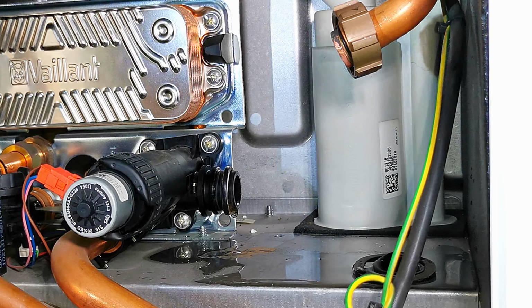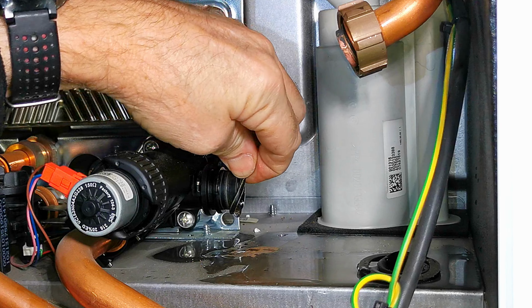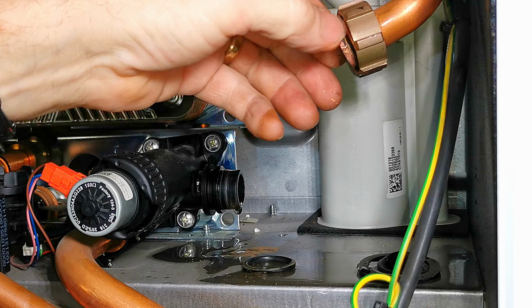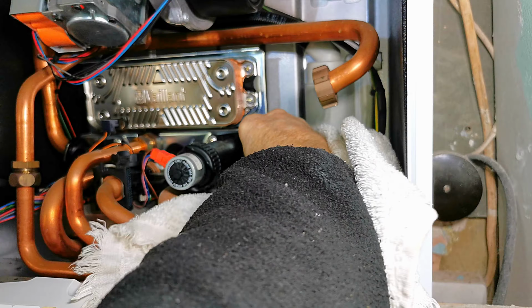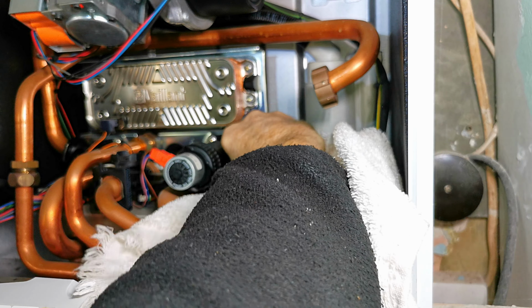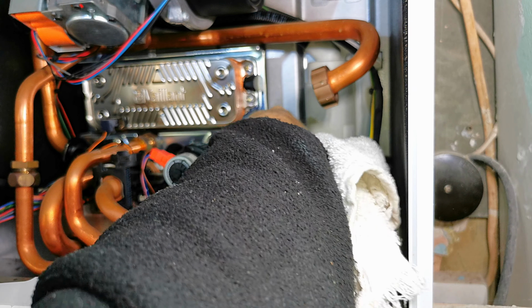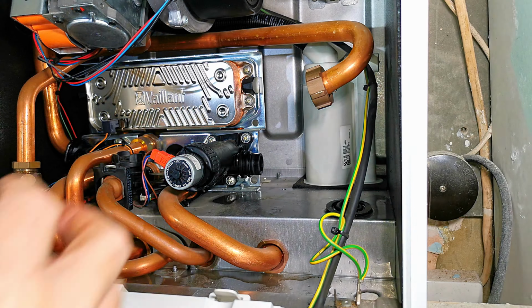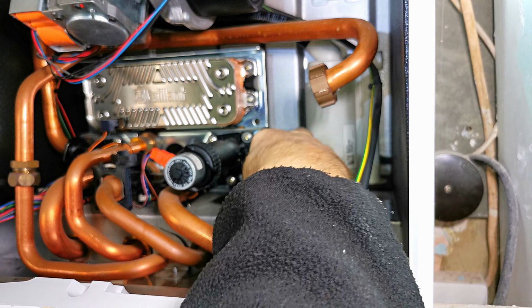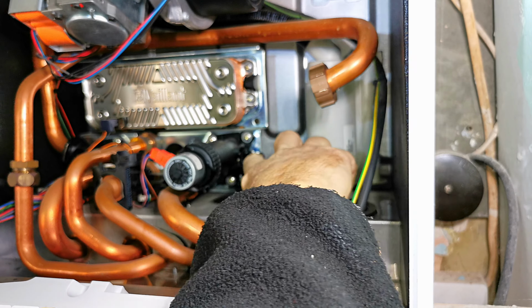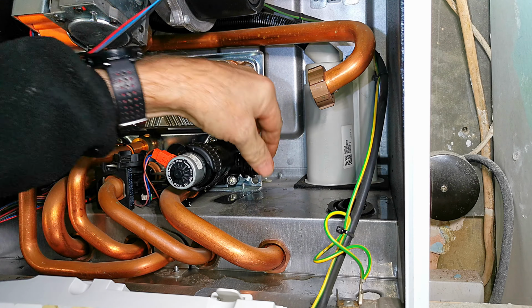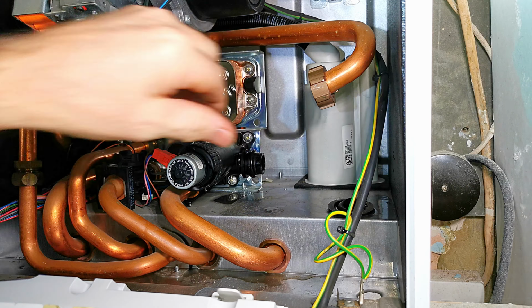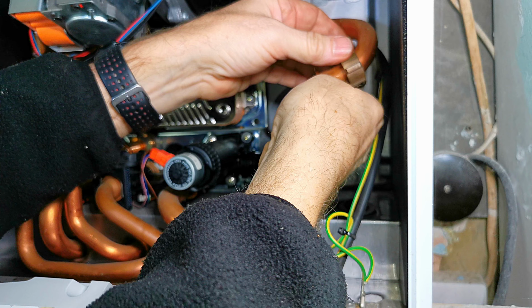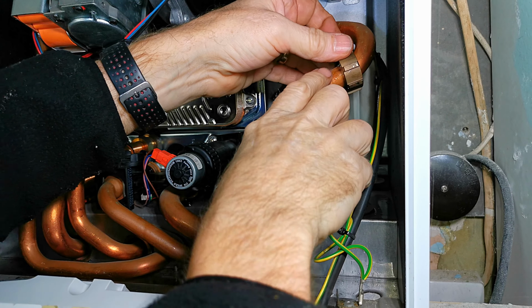I've then removed the old O-ring from the diverter valve, and I'll also remove the old O-ring from the return pipe. Give both connections a bit of a clean to make sure there's no bits of dirt on there. Then once again get some silicone grease and wipe it around both the fittings. That's the diverter valve done. And there's the new O-ring fitted on the diverter valve. And again I put some more silicone grease and fit the O-ring onto the return pipe.